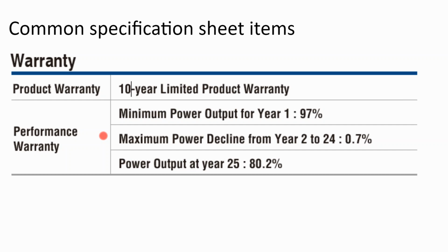And so just be aware that the performance warranty is more of a performance indicator than anything else. If your panel drops below 90% at year 6, and you have that stair-step warranty, the manufacturer may come back to you and say, well, here's a check for the pennies difference in lost production that you've lost on that one solar panel. But before it's eligible for the warranty, we want you to do all this thermal testing and IV testing, because it's going to be real costly for us to initiate our take-back process. And that's, again, conversations you really only get into with commercial projects where you're working directly with the manufacturer.